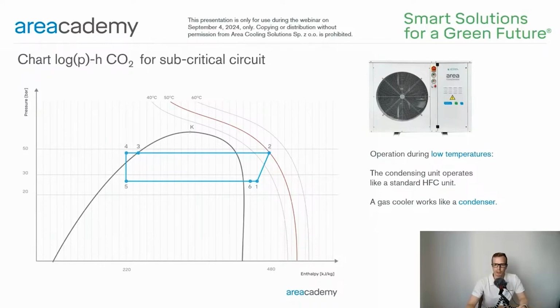The operation of a transcritical unit from a thermodynamic point of view strongly depends on the ambient temperature. When the ambient temperature is low, for example during the winter, the unit works like a standard HFC unit. It means there is a condensation process of refrigerant here, because the pressure is below the critical one. Therefore, the gas cooler in these conditions works like a standard condenser.